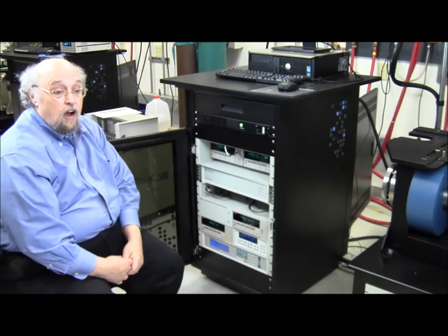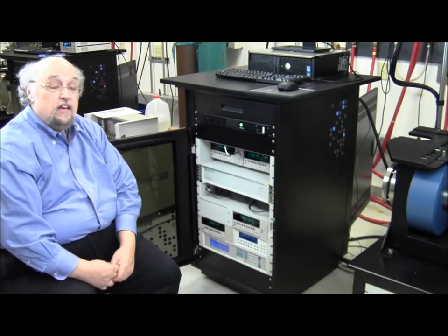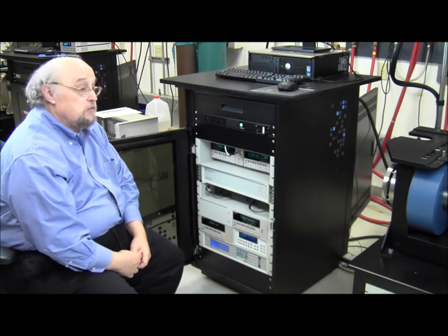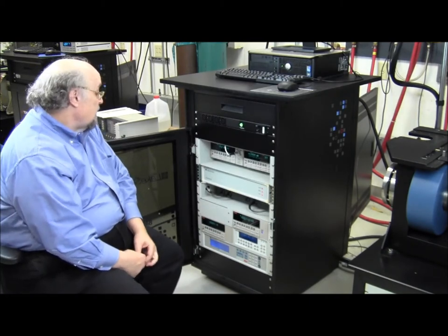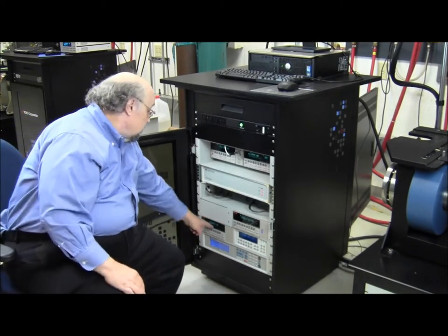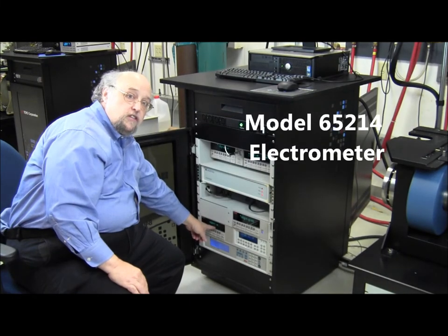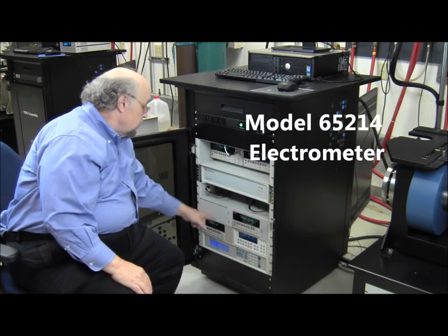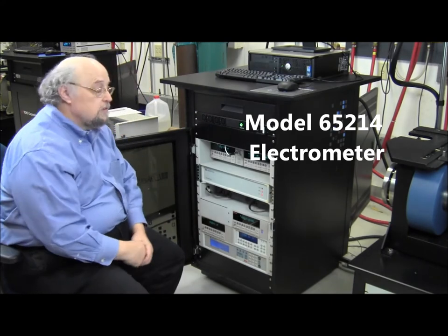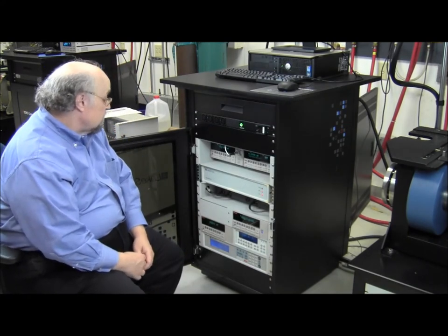If you need to measure higher resistances you can add the high resistance option to the system. That does two things. One, it gives you a Keithley electrometer for measuring the current. So we make sure that when we apply a current, we measure the same current and make sure there's no leakage in the system.